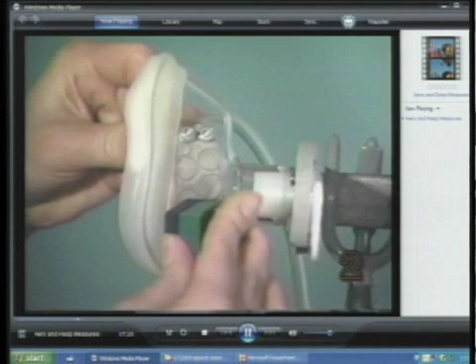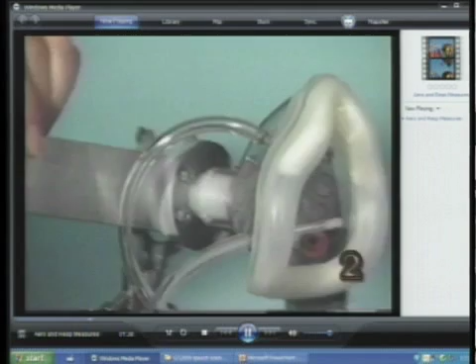This particular transducer has a wideband frequency response in that it picks up higher frequency flow components than most typical air pressure transducers. It's because of this response that it produces a waveform that looks very much like a voicing waveform. Notice that we have a second pressure tap which leads to a second transducer with a lower frequency response. It's from this transducer that we generate the average airflow and the volume waveforms. The third tap on the mask right here is connected to another pressure transducer optimized for measuring intraoral air pressure. Inserted inside the mask at this tap is also a small hollow polyethylene tube that will be placed into the oral cavity and picks up the intraoral air pressure values.